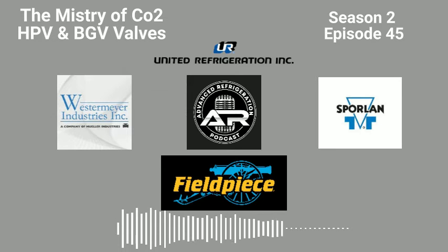It's transcritical. So when we're above that, CO2 becomes incredibly inefficient. So that is a liquid vapor mix, basically. And if you were to try to cool with that high pressure, unstable fluid, the cooling properties of that is extremely poor. So your cooling per pound circulated would be terrible. So it would be completely inefficient. So what we do with this is we have to bring that CO2 back down to a stable, workable state. So the way we do this is we need to bring it back down below 87 degrees.